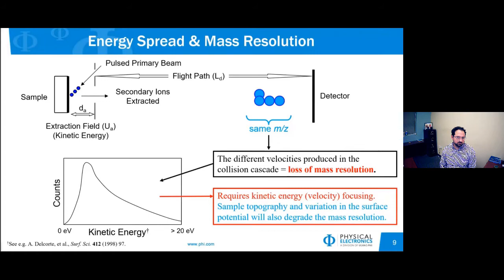Some of the ways we can focus these ions to get better mass resolution is by using an energy compensating TOF analyzer. There are 2 main types of commercially available energy compensating analyzers. One type is a Reflectron. We have the same mass to charge ion coming off with different energies, and as it's extracted, it comes in contact with an electric field, an ion mirror. The high energy ion will take a deeper path into the ion mirror, and the low energy ion will take a shorter path. As they're directed back towards the detector, they get refocused because of these different flight paths.